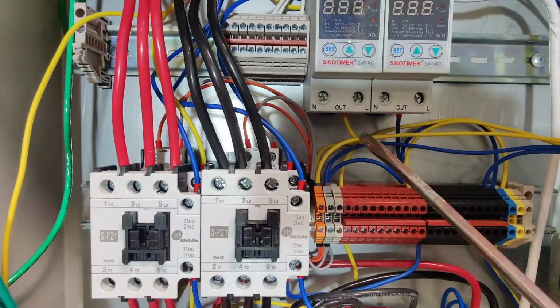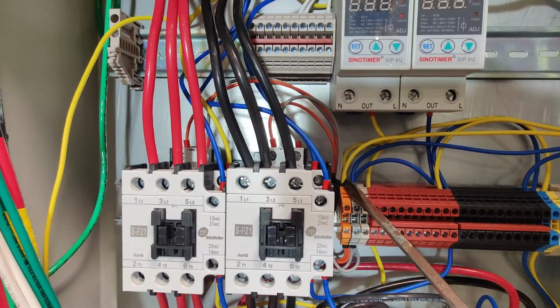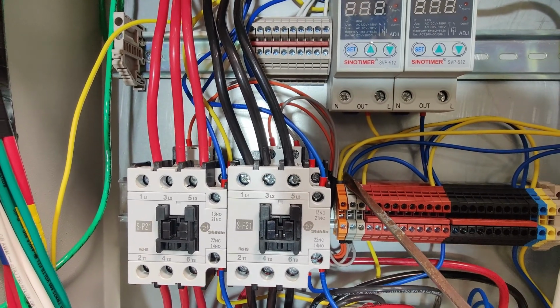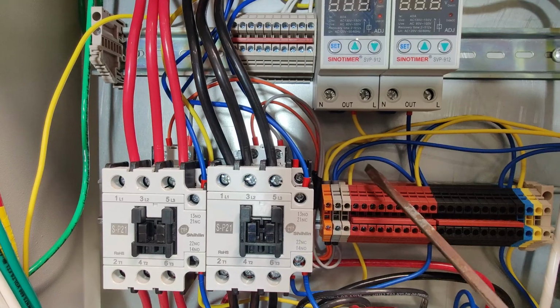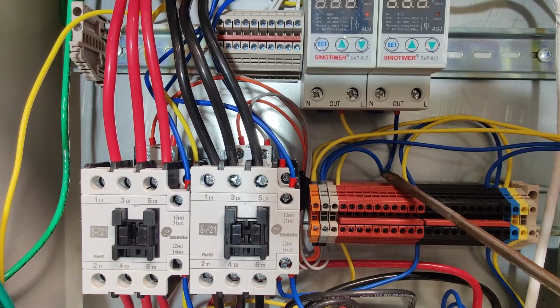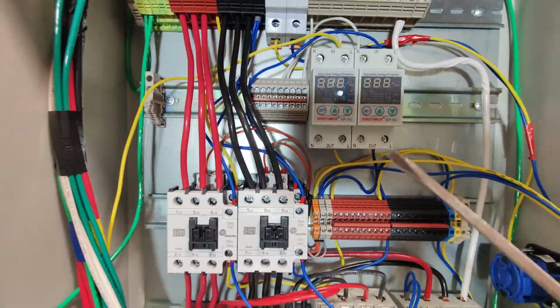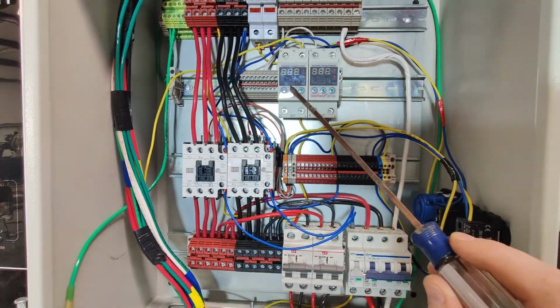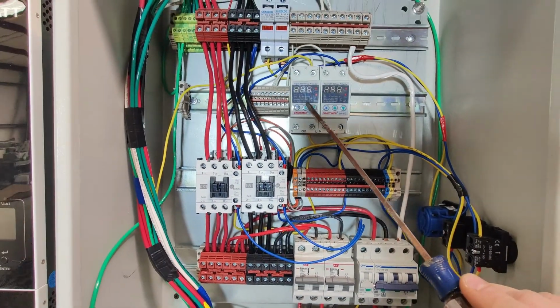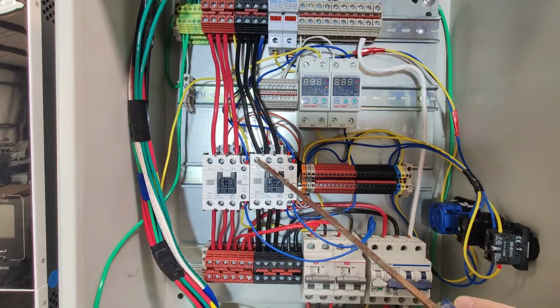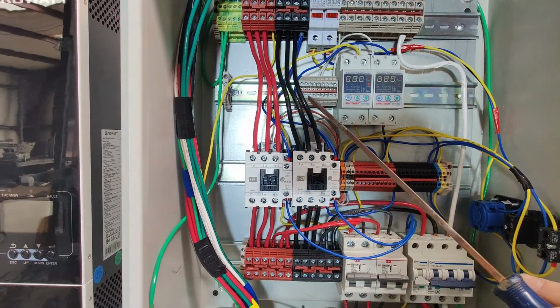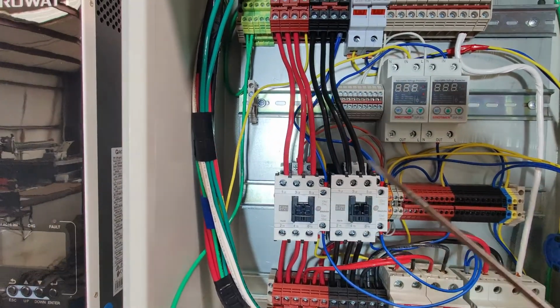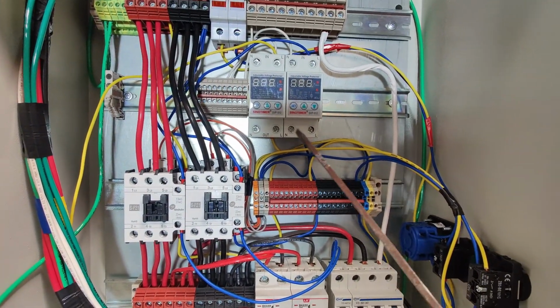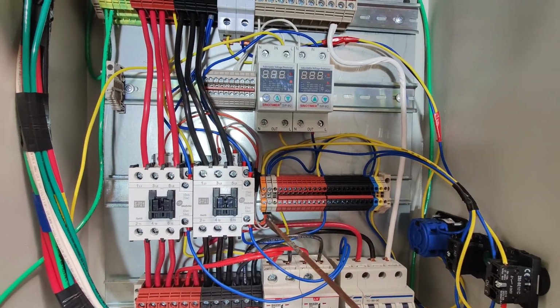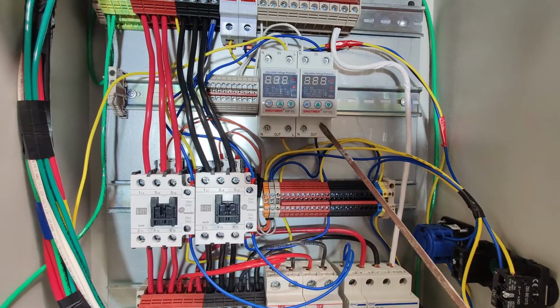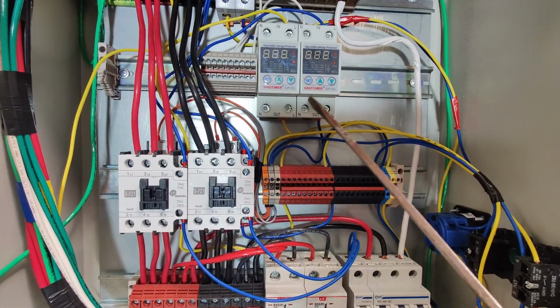But you'll notice some extra wires coming in here, and essentially this is a bypass. We're going to use some momentary switches to operate that bypass, and that bypass allows us to temporarily bypass the voltage protection relays. The voltage protection relays themselves are set up for 120 volts, so they won't actually activate and turn on until they see 120 volts. However, these are 240 volt contactors. They need 240 volts to turn on. So we take each leg out of the bottom side of the voltage protection relay, run it into here, and if you measure across these two, you'd see that there's a 240 volt difference in there.